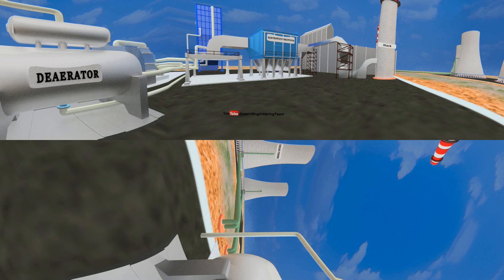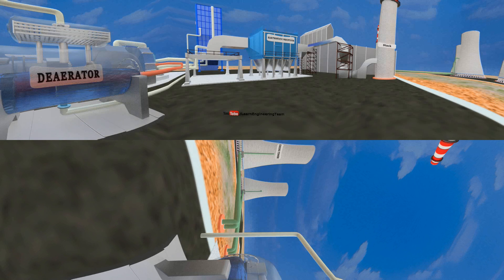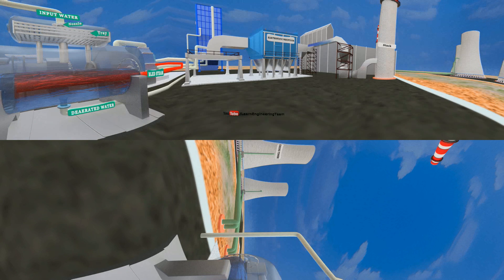Turn your head to the left. The equipment you see here is called a deaerator. The main function of a deaerator is to remove dissolved gases from the feed water. Feed water is sprayed into the deaerator with the help of a nozzle. Steam bled from the turbine is used to absorb the dissolved gas.